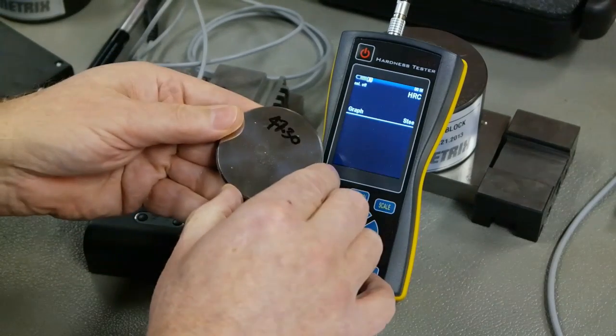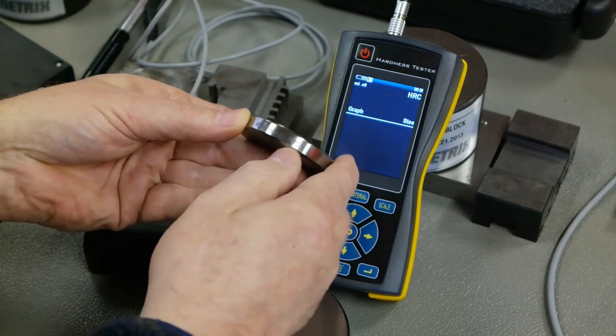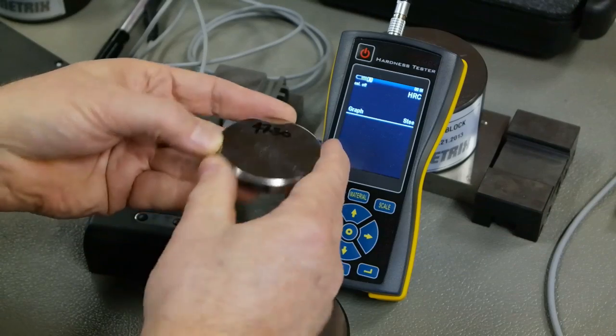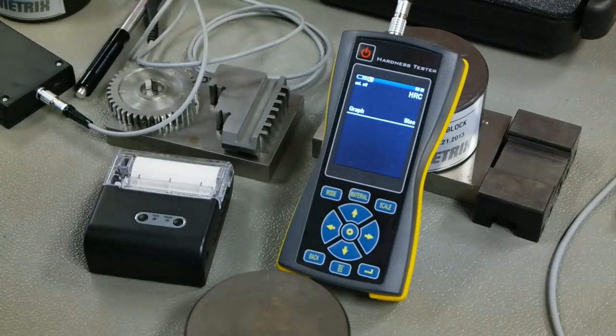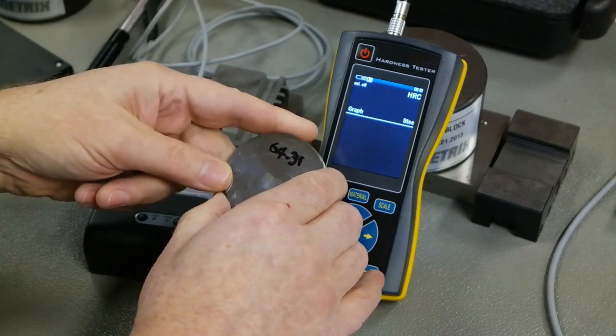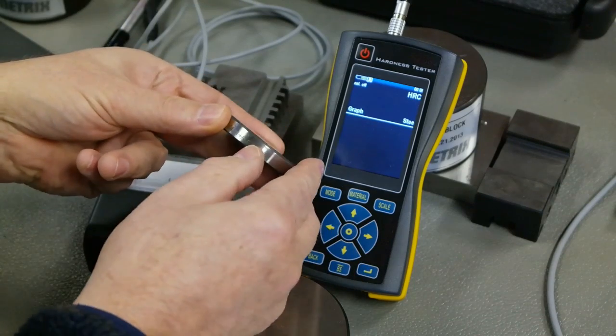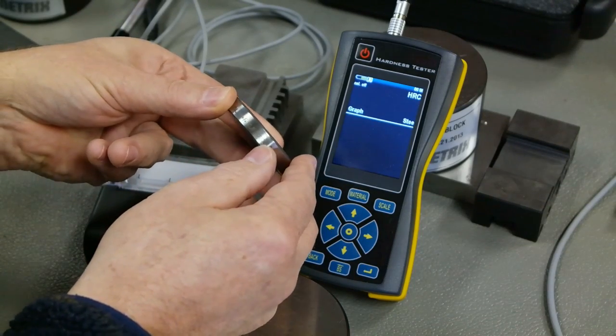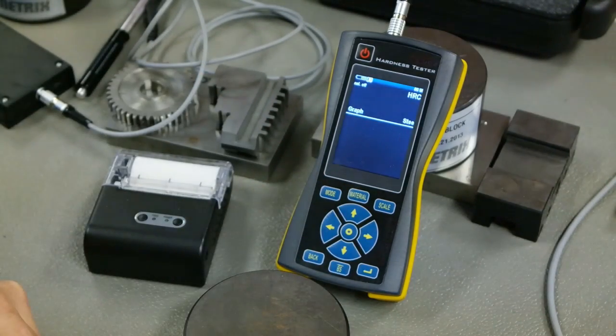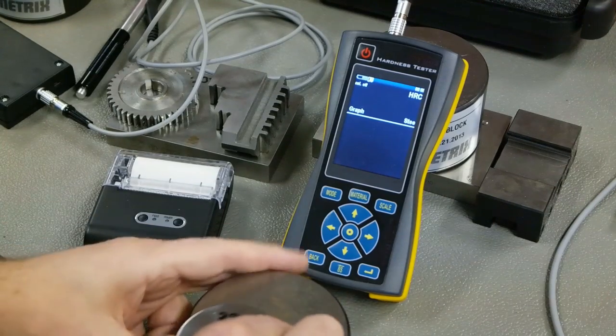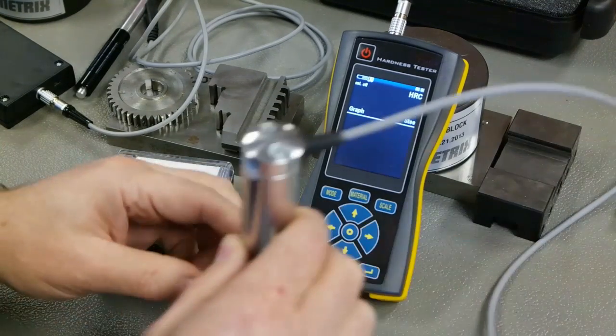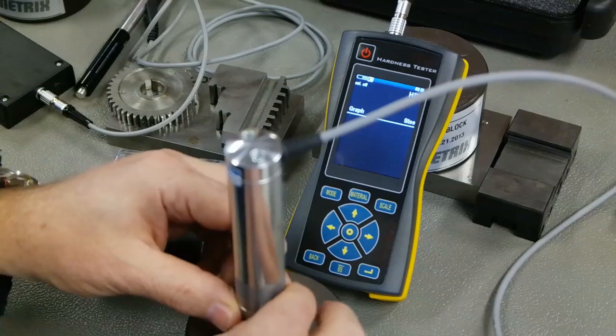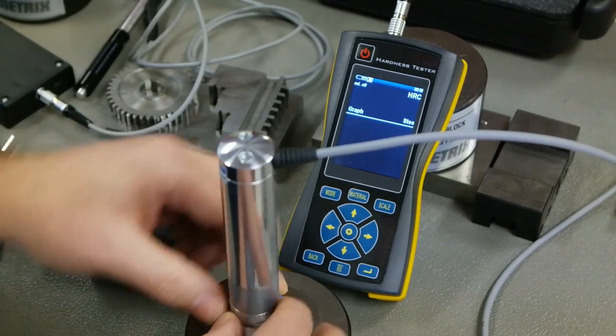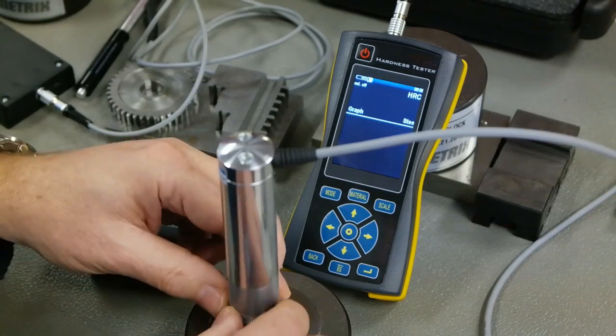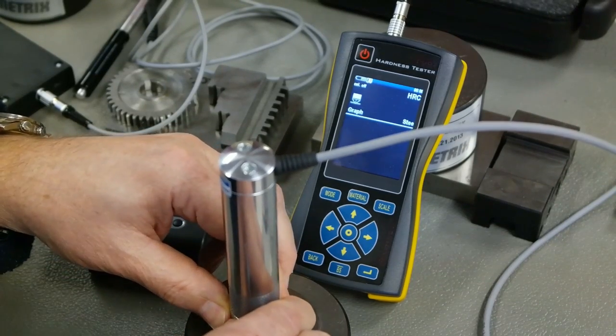and I have a 47.3, and its tolerance is plus or minus 1 HRC as well. And then lastly, we have a harder block, a 64.31, and it's plus or minus 0.5 HRC. So just starting with the first test block here, softest one, bring the probe over. Hopefully the cable is not in the way, you can still see the display. There, with the puck here, if I press down on the sides, I can get a very nice reading.